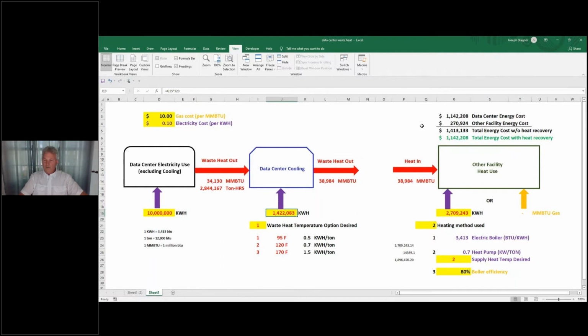Well, suppose right next to the data center, and this isn't the case many times, there is a facility, say a commercial laundry building or an apartment complex, that uses a lot of hot water for baths and kitchens and laundry, whatever it may be. I'll call that an other facility. And suppose that facility just happens to use each year the same amount of heat that your data center is throwing away. So it needs to produce that amount of heat. Well, it could do it with natural gas, and a lot of them do use natural gas around the country. So to make that much heat in an 80% efficient hot water heater or boiler, you'd have to put in this much natural gas, and at $10 a unit, that'd cost $487,000 of energy for that facility sitting next to you to make the heat you're throwing away.